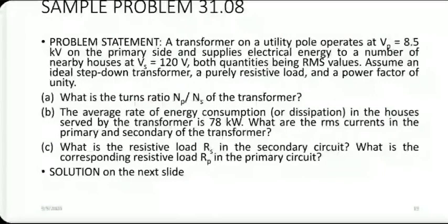How much current will be in the primary and secondary? In the primary, total power is 78,000 watts and power factor is 1. Power is V times I, so VRMS times IRMS times cos phi, with cos phi equal to 1. VRMS in the primary is 8.5 kilovolts, so you take 78,000 watts and divide by 8,500 to get the primary current.